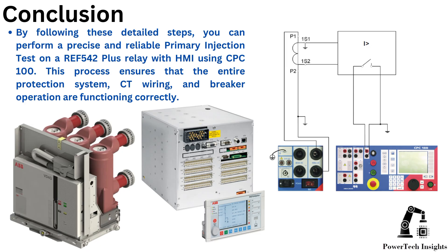Troubleshooting and common issues: If the REF542 Plus does not trip, check CT polarity and connections, ensure the overcurrent setting is lower than the injected current, and verify that relay protection is active. If the REF542 Plus trips at the wrong current, cross-check the CT ratio settings in the relay, check for loose connections in the CT circuit, and ensure that CPC100 is outputting the correct test current.